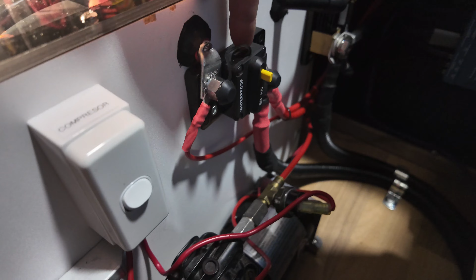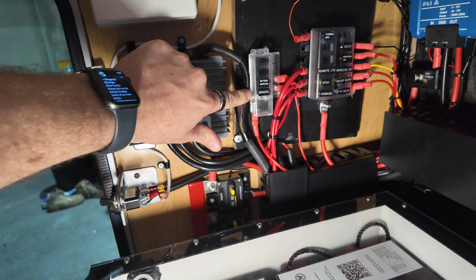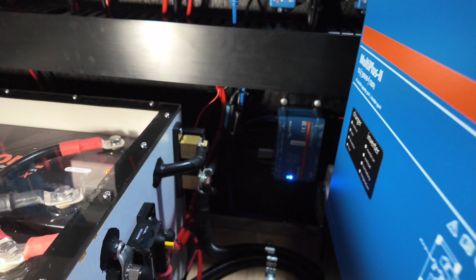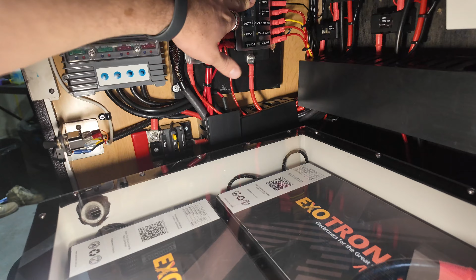Over this side we've just got some more fusing, so there's an inverter and main switch circuit breaker. This cable on the battery side runs this fuse panel, which has our battery monitor and our brakes on it. That's purely so our servo system doesn't disconnect - it'll only turn off if the batteries are flat, but if the inverter trips, the battery monitoring system won't trip, it'll stay on. And this solar panel is just powered off the other side of your main switch.